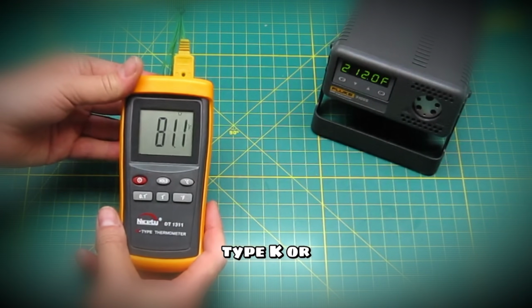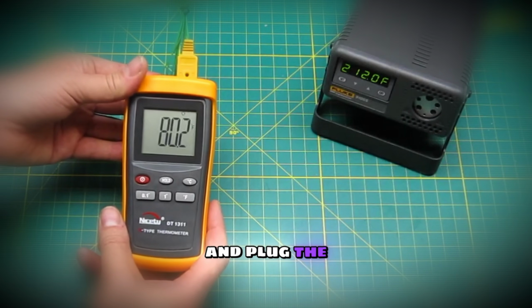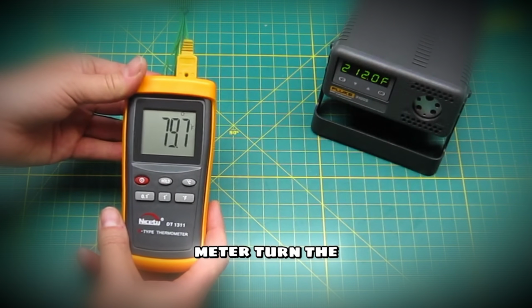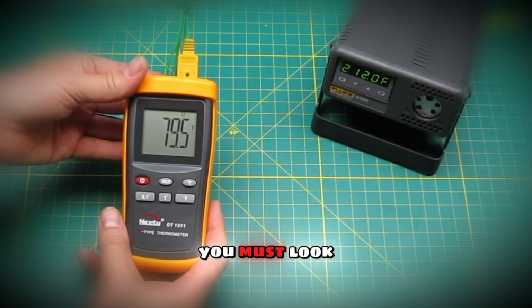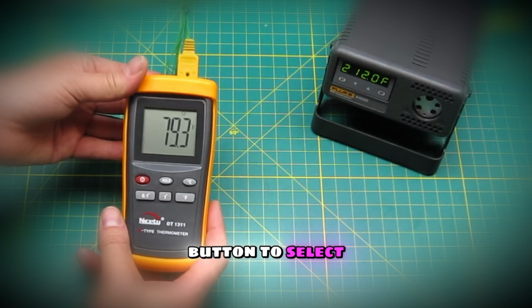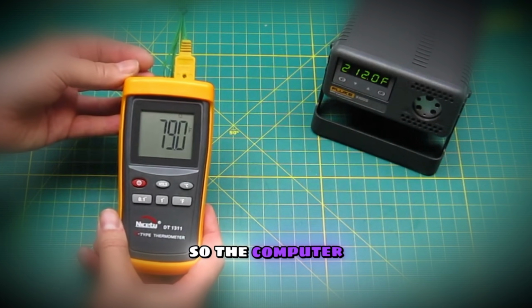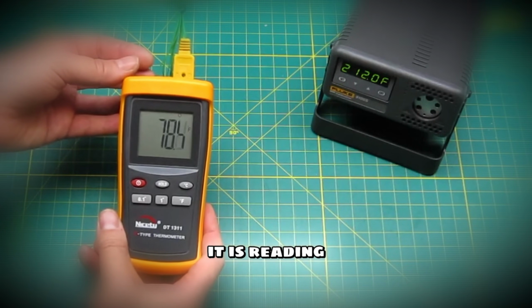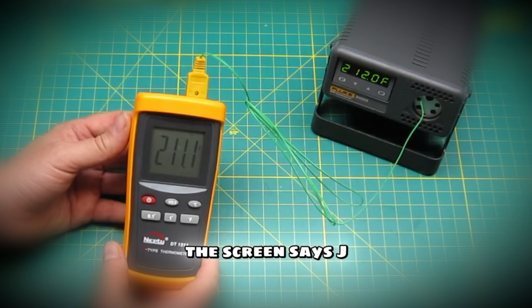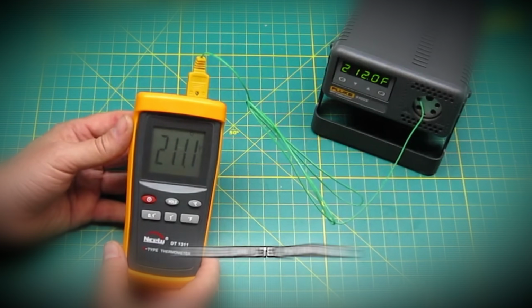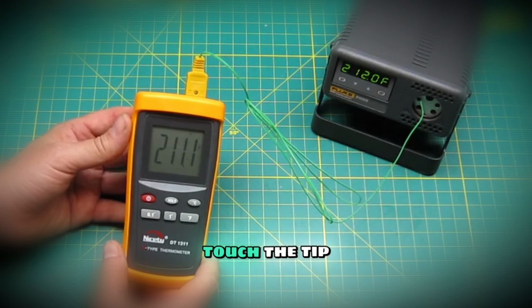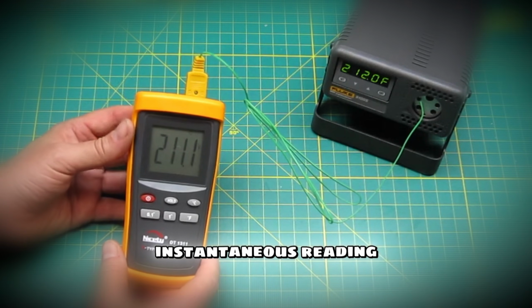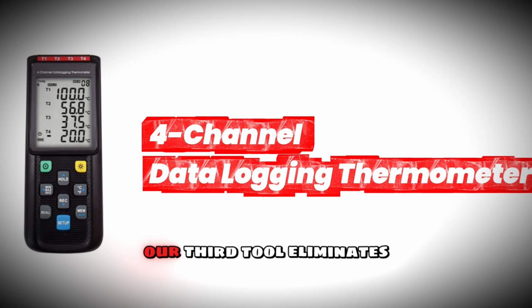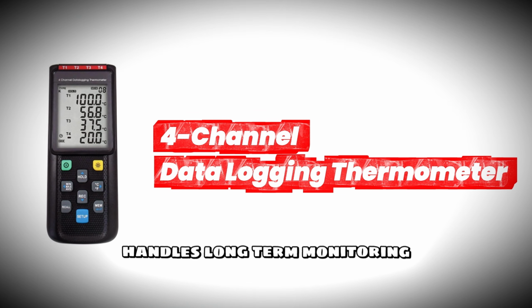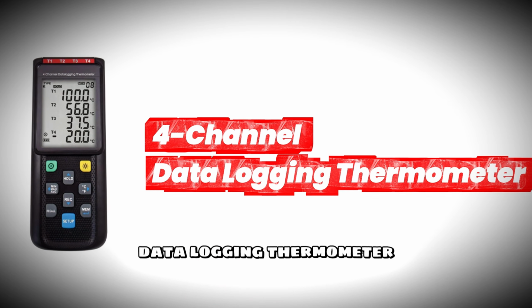First, grab your Type K or Type J probe wire and plug the two-prong connector into the top of the meter. Turn the power on. You must look at the screen and press the mode button to select either K or J so the computer knows which metal it is reading. If you plug in a K-type probe but the screen says J, your calibration will be completely wrong. Once matched, touch the tip of the wire to the surface you are testing, and you will get an almost instantaneous reading.